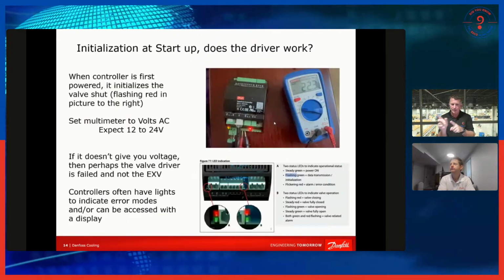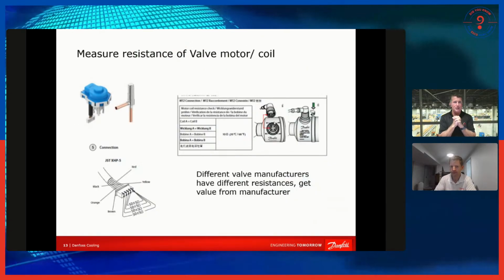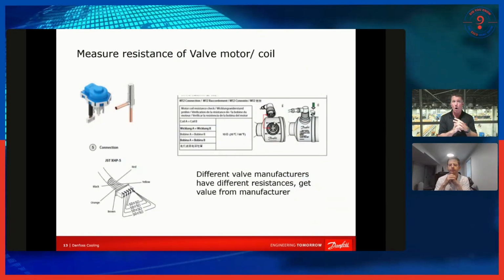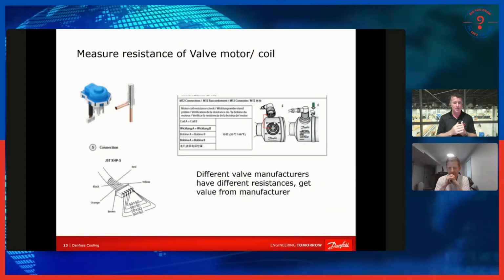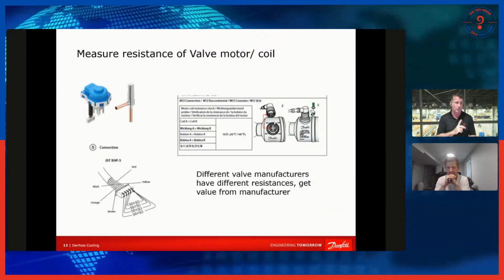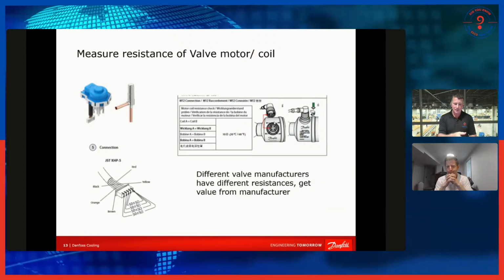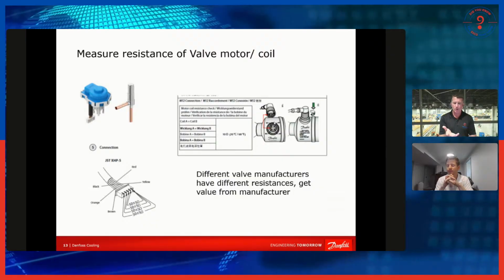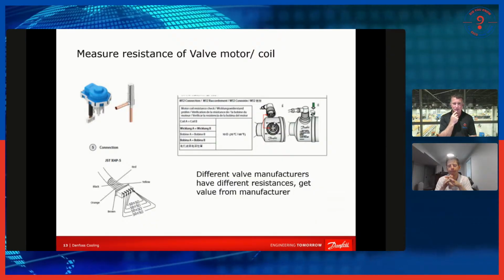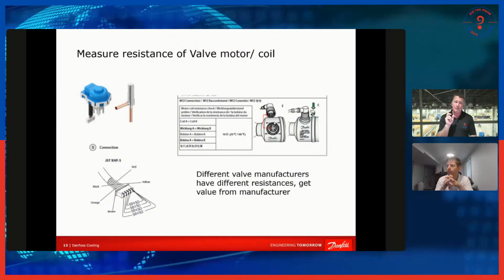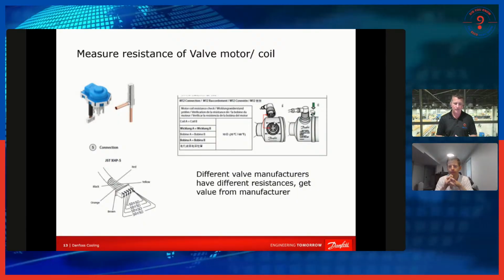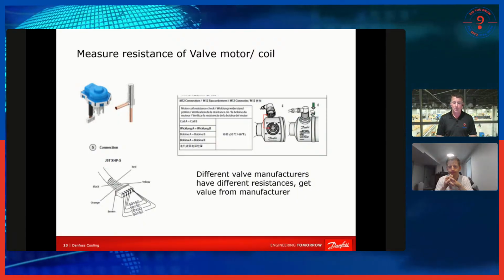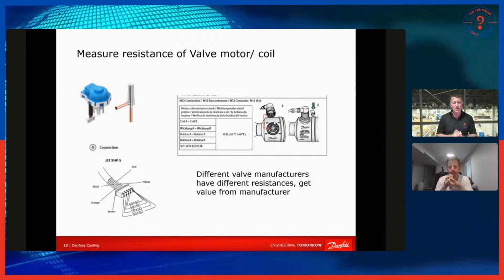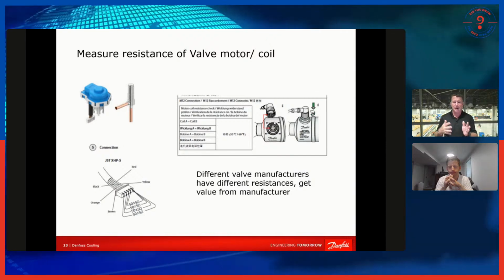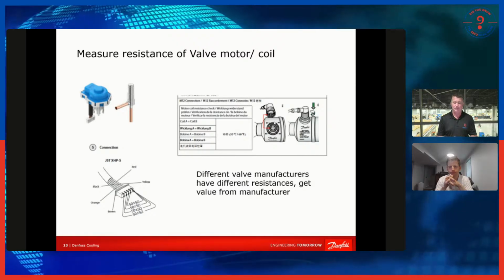Brian, before you get to that next one, I have a scenario that I'm hoping there might be some more information on. It's something I've witnessed in the field before. Okay. Say we had four winding connections or five winding connections, and we found one of those pairs to have an open resistance, what would we potentially see in the operating of the valve?